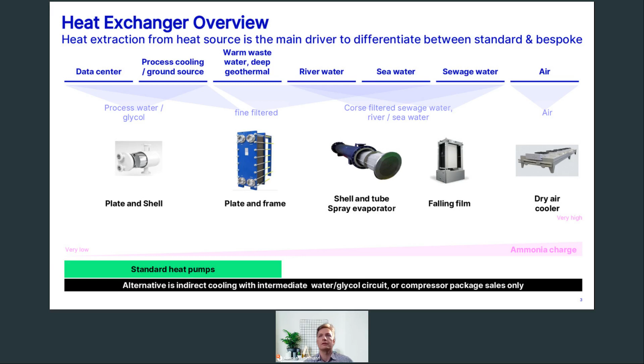Regarding filtration, there have already been a couple of very interesting presentations on how to make sure that the heat exchangers stay clean. That's also what we see from the project that we are involved in, that there needs to be focus on making sure that the heat exchangers do not foul up, because you don't always have clean source water. So something like a backflush filter, which you can flush whenever the pressure drop over the filter starts increasing, so you don't need to take the filter apart, but it can be cleaned while in operation. Another thing we have done is to have reverse flow.